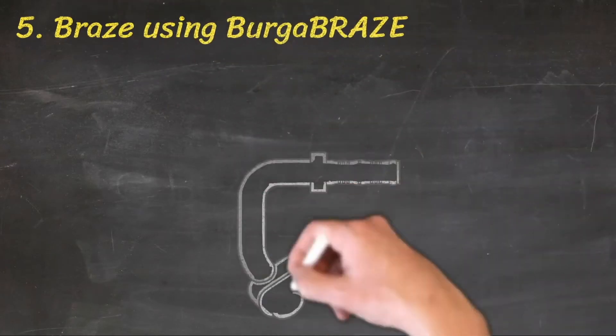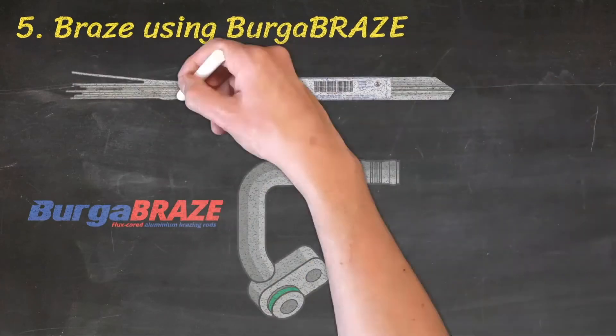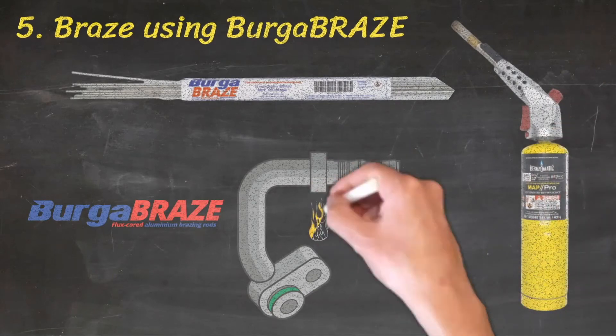Step 4: Place the BurgaClip braze-on tail onto the prepared pipe. Step 5: Braze using BurgaBRAZE flux-cored aluminium brazing rod for aluminium, or a quality 45% silver solder for steel, using a hand-held propane or butane gas torch.